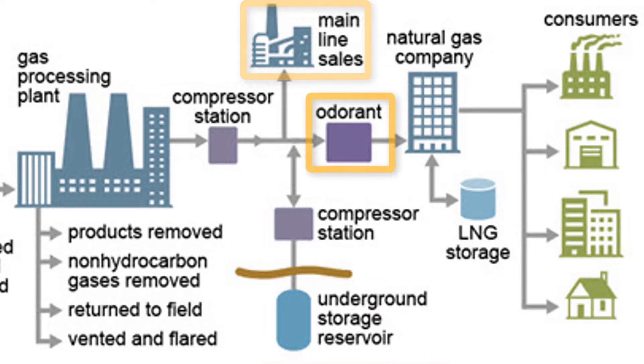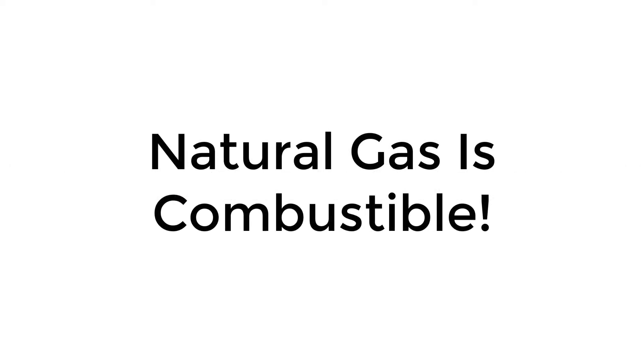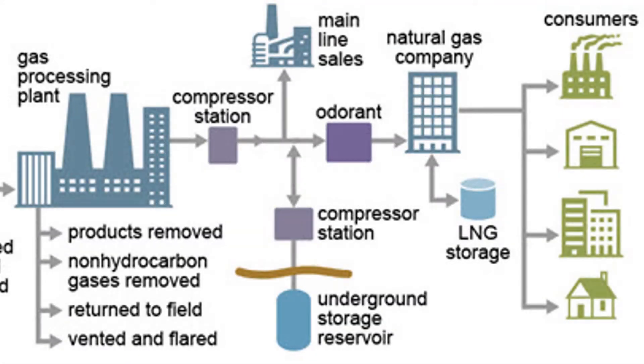The odorant stage is where we add odorizer to the gas stream. Natural gas in its natural form doesn't smell, however it will still combust if mixed in air and given an ignition source. What we actually do is add a very strong smelling odorizer to the gas stream — typically sulfur, which has a very strong egg smell. That way, if the gas does leak in your home you'll be able to smell it, avoiding a situation where gas leaks without anyone knowing.